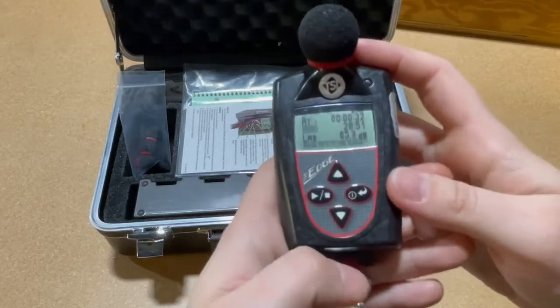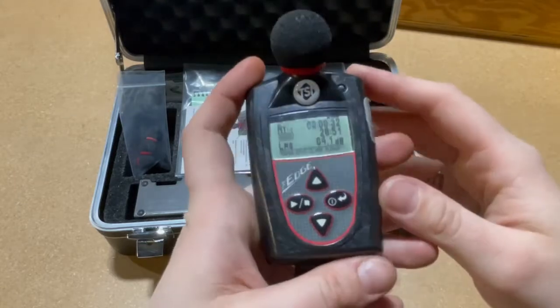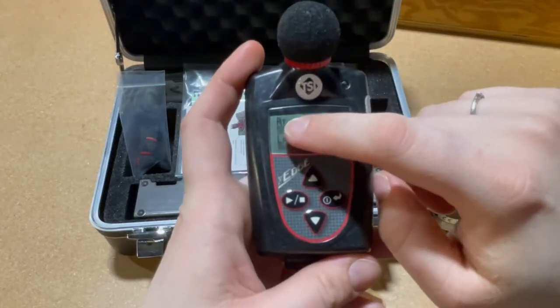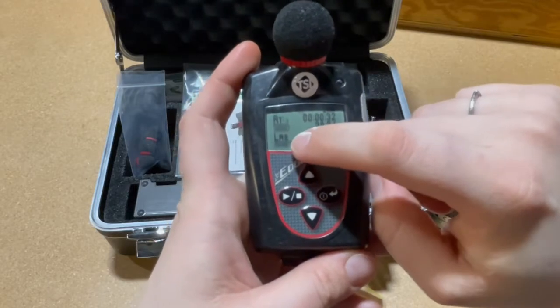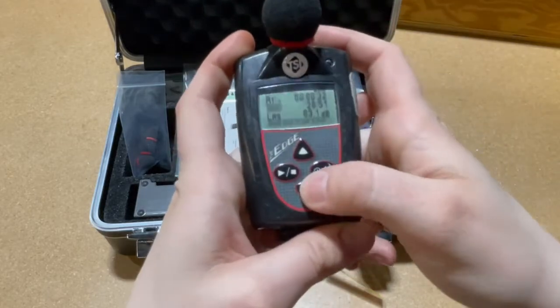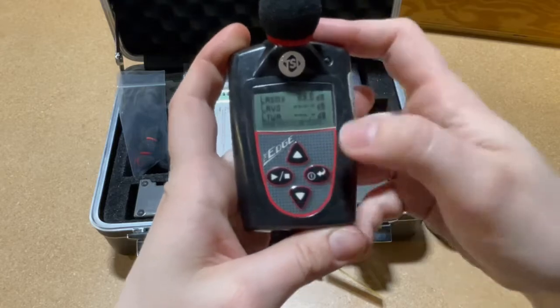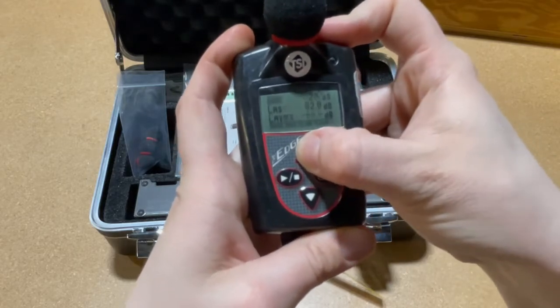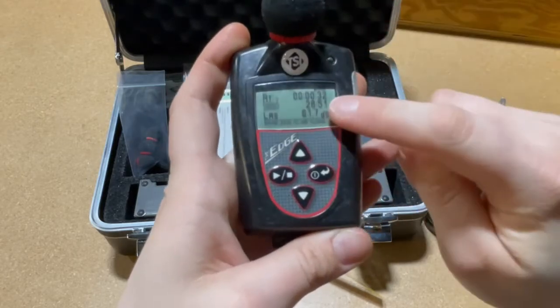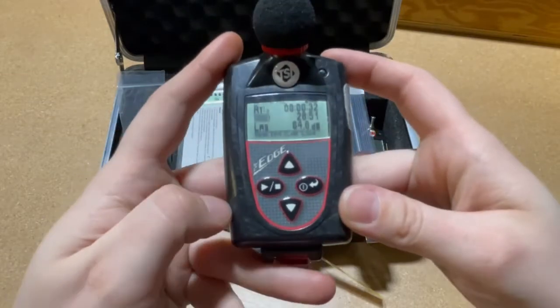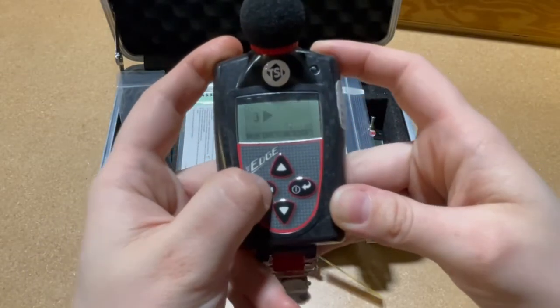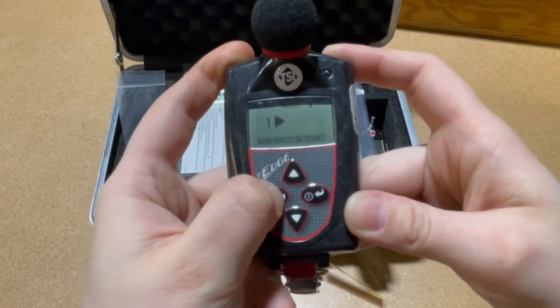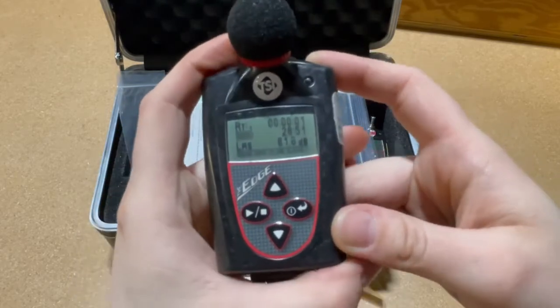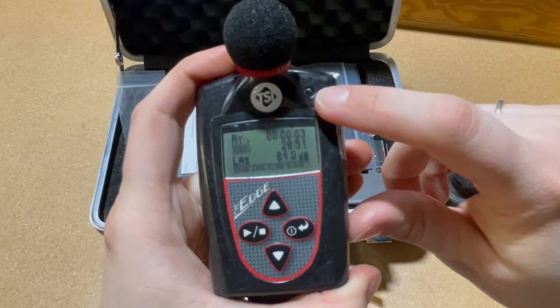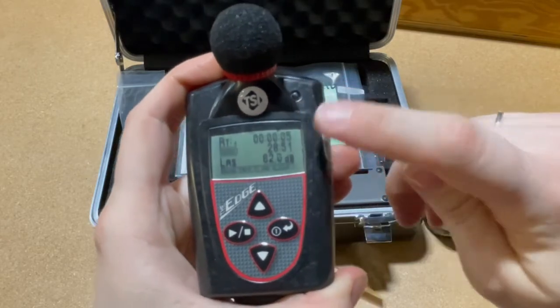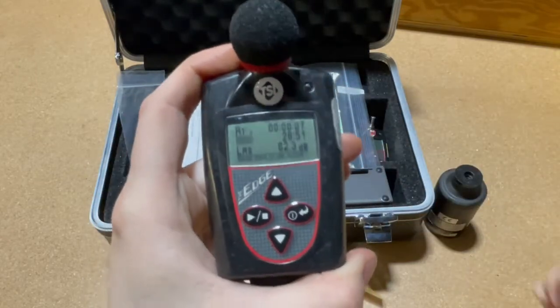Now, to record data or data log, we're going to make sure that the screen is showing RT, the battery, and LAS. So if the screen is, say, down here, you'd want to just scroll up until you see that. So once we're there, we're going to hold this play button until the countdown stops. At that point, this light will change to blinking green instead of red, and that means that you're data logging.